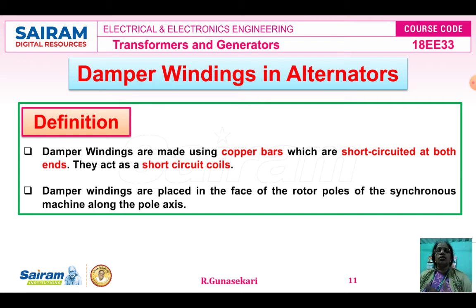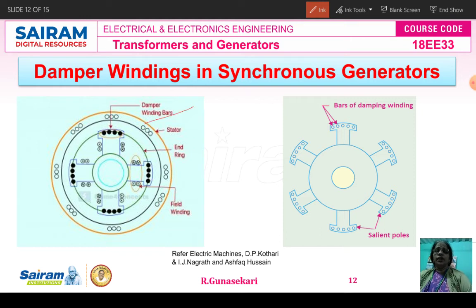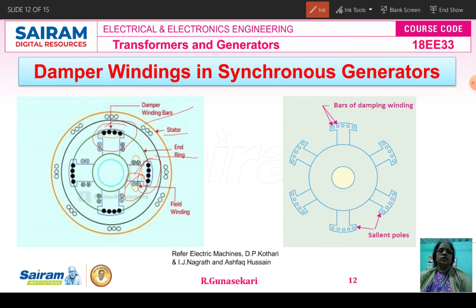The damper winding is nothing but a short-circuited copper bar — short-circuited at both ends, forming a short-circuit coil. Normally, the damper winding is placed on the rotor pole face of the synchronous machine, either synchronous motor or synchronous generator, along the pole axis. Looking at the circuit diagram, you can see the damper winding bar — a copper bar short-circuited at both ends. This is the stator, this is the end ring, and this is the field winding. The damper winding is placed on the pole face.